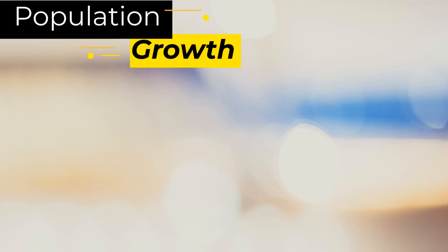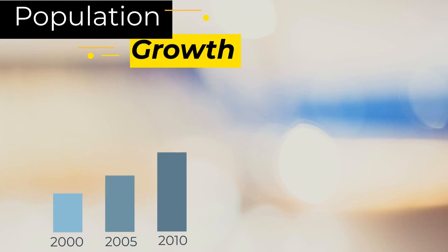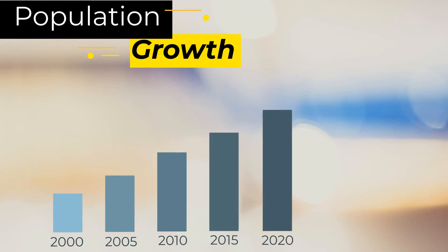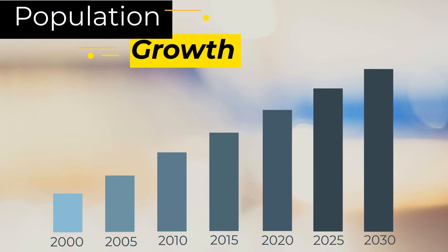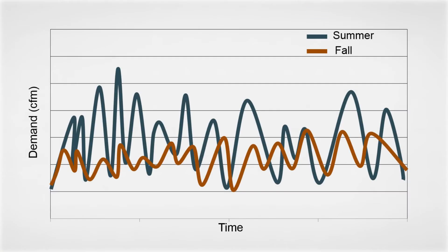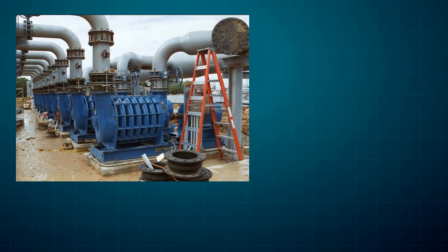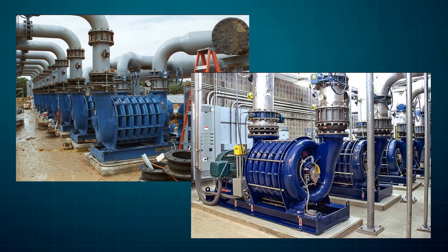A big part of the problem is the need to install a blower system that will meet increasing plant demand projected over 10, 20, or even 30 years. On top of that, treatment plants face daily and seasonal variations in air demand. So many aeration systems have been designed with very large blowers that run well below their best point of efficiency most of the time, and the benefits of more efficient blower designs are lost.